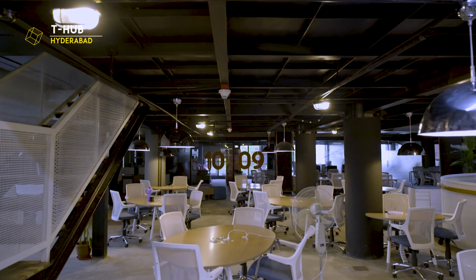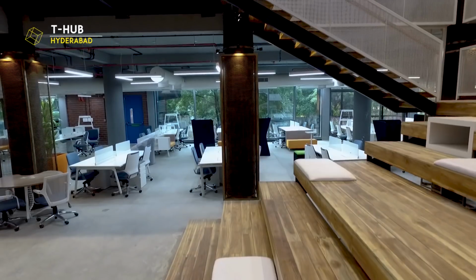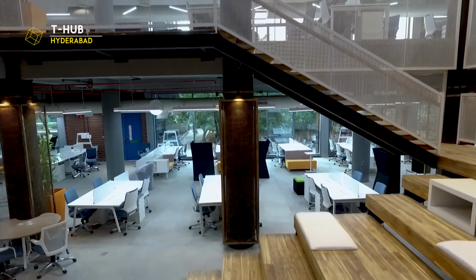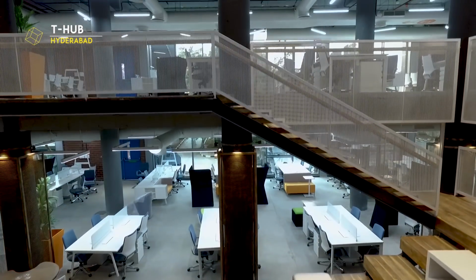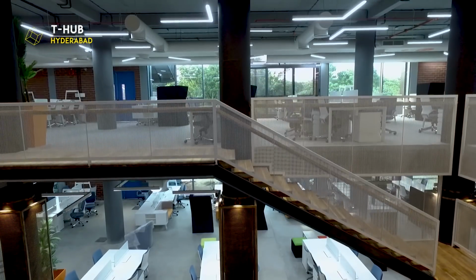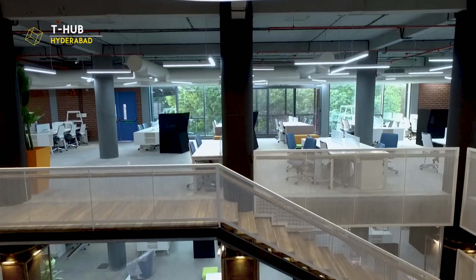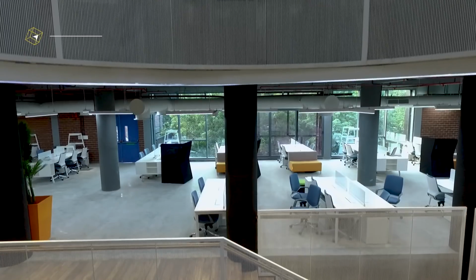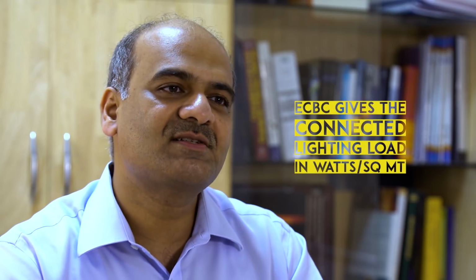So how do we save energy on artificial light? ECBC gives a very simple parameter, which is watts per meter square of connected lighting load. That means if I have an area of say 100 meters square and 100 watts of electrical lighting fittings in that area, then 100 watts divided by 100 meters square makes it 1 watt per meter square. So like this we can calculate the connected load of lighting per meter square, and there is a cap given to that.